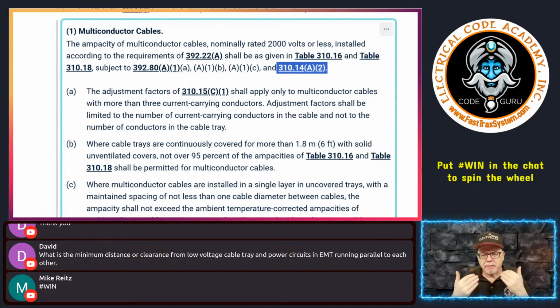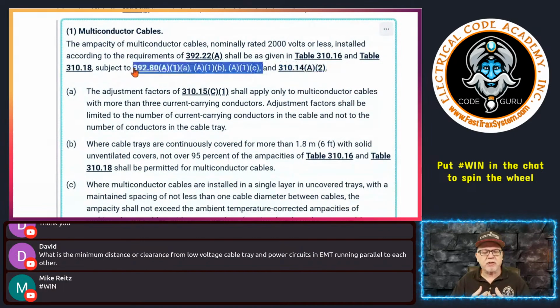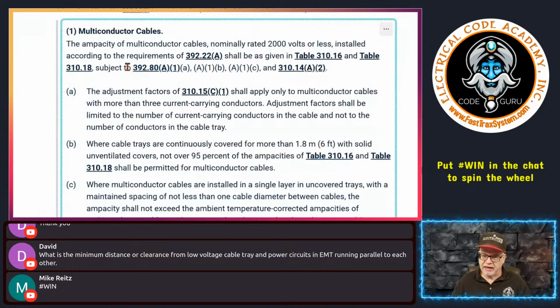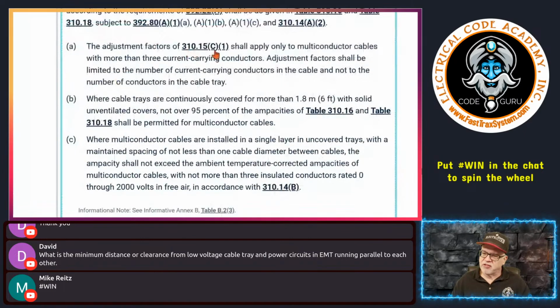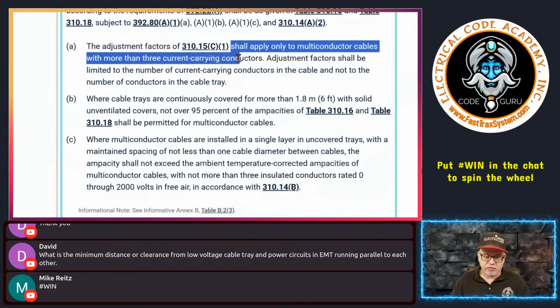But just remember, to keep from being confused, these are the ones that typically play a role when you're doing the ampacity for multi-conductor cables inside of a cable tray. Here's the first one, A. It says the adjustment factors in 310.15(C)(1), and again, that is the bundling rule, okay? Shall apply only to multi-conductor cables with more than 3 current carrying conductors.